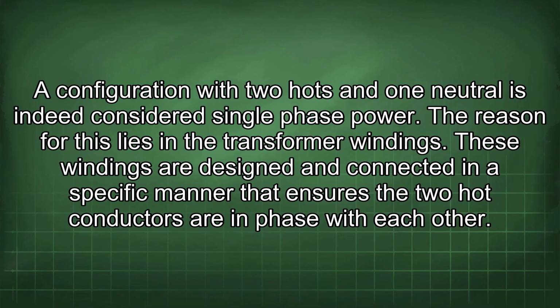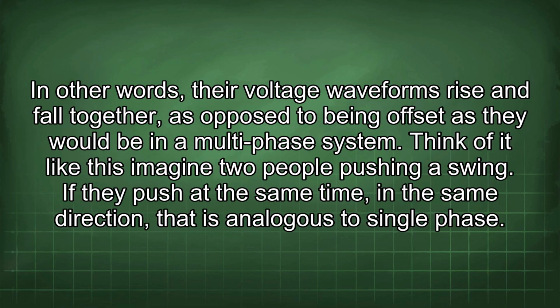A configuration with 2 hots and 1 neutral is indeed considered single-phase power. The reason for this lies in the transformer windings. These windings are designed and connected in a specific manner that ensures the 2 hot conductors are in phase with each other. In other words, their voltage waveforms rise and fall together, as opposed to being offset as they would be in a multi-phase system.